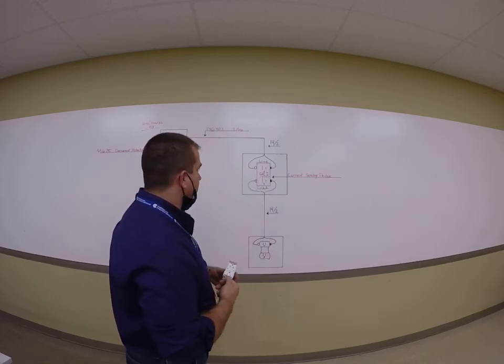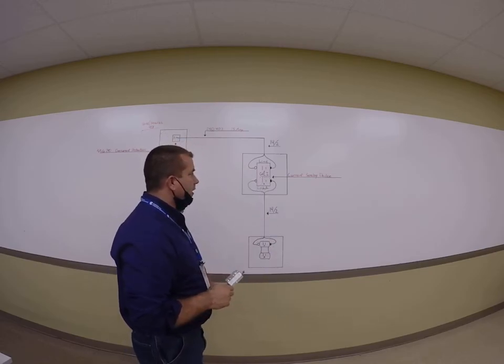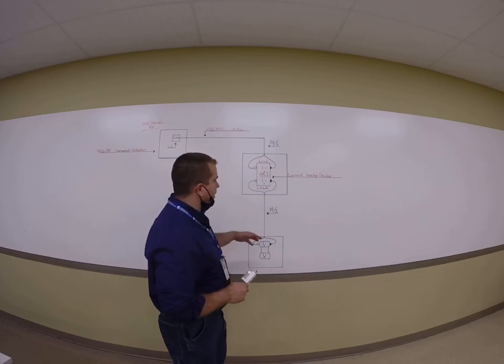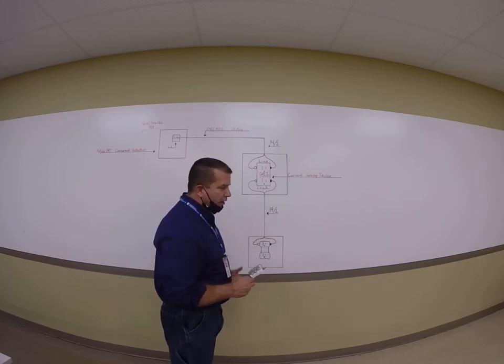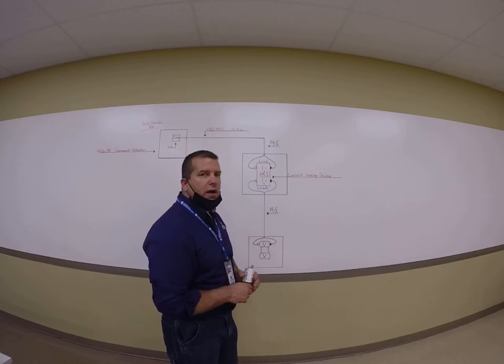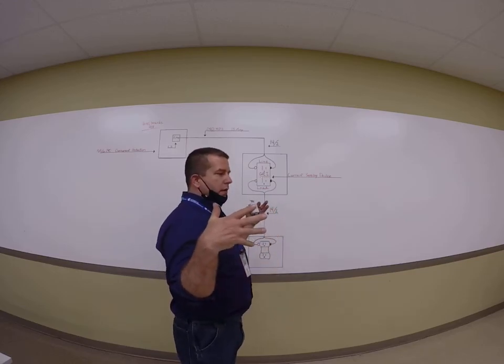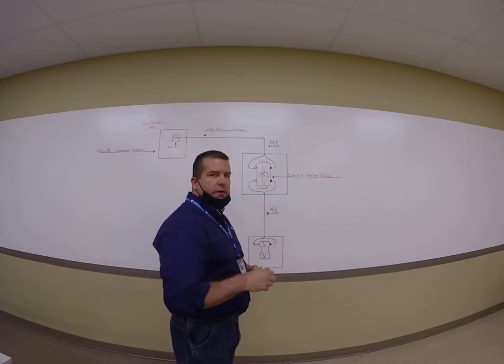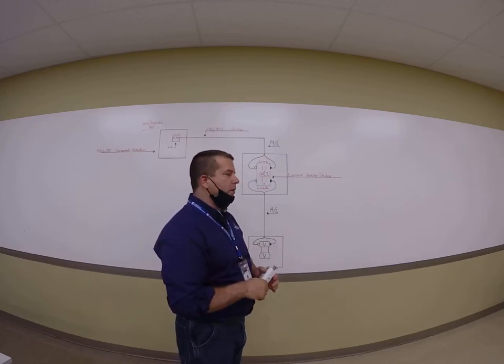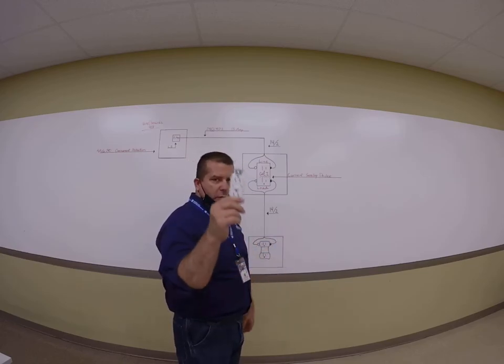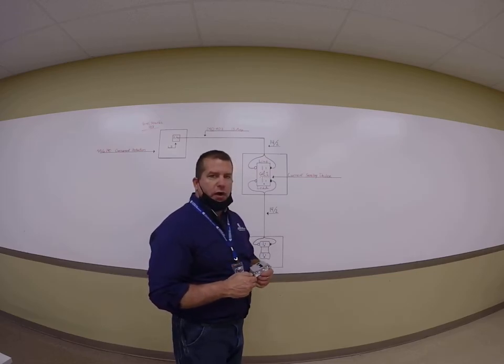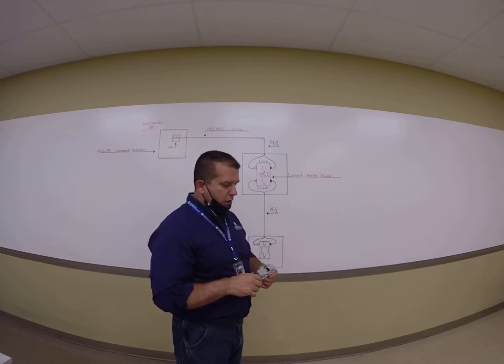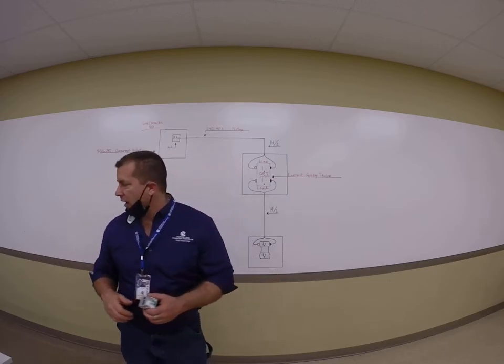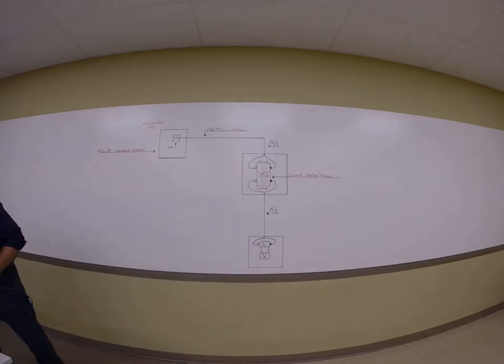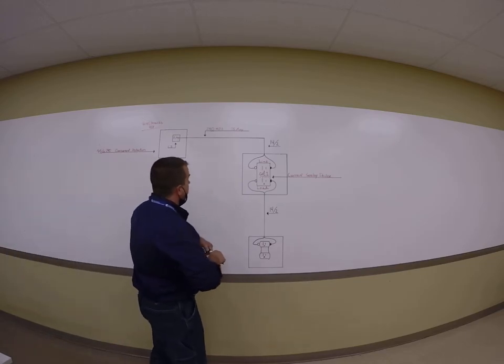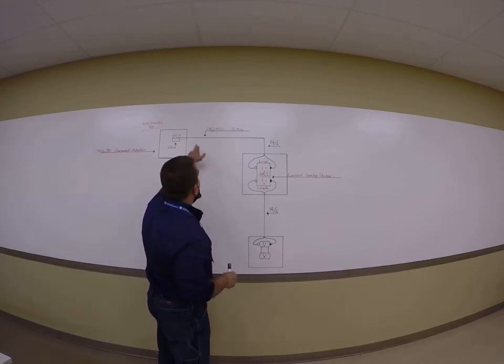So when I look at this ground fault circuit interrupter, the first thing I'm thinking about is guys are normally tying circuits in and they splice wires all together and they add tails. So your conventional way of wiring something is you would take two blacks, tie them together, put a tail, go to the receptacle. And every time we get a student that hasn't wired one of these in a while, they do the same thing and they end up wiring it wrong, or they put the wires in the wrong place.